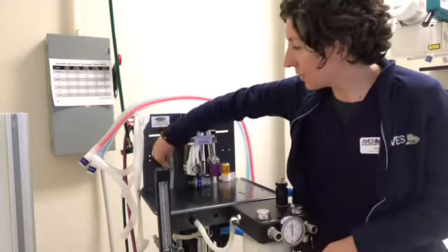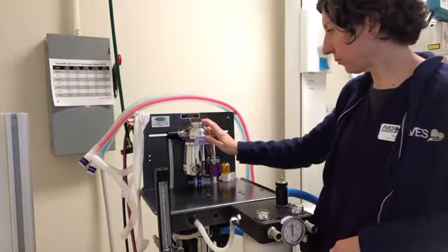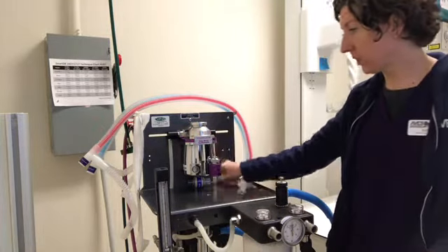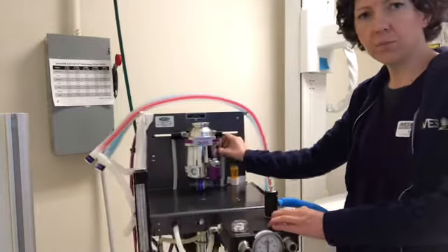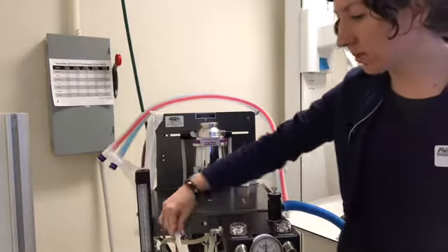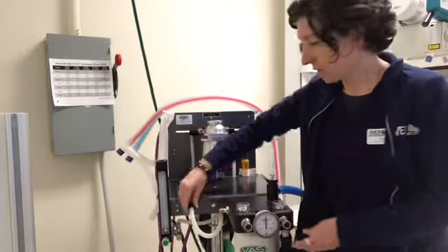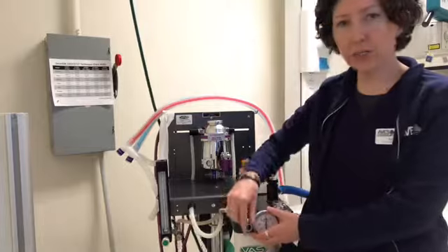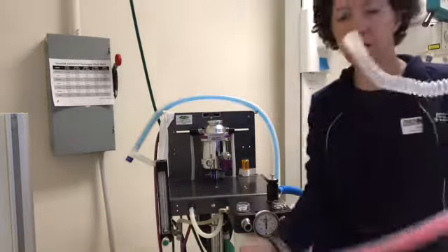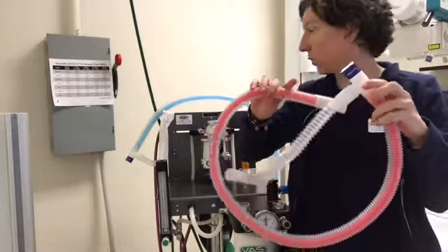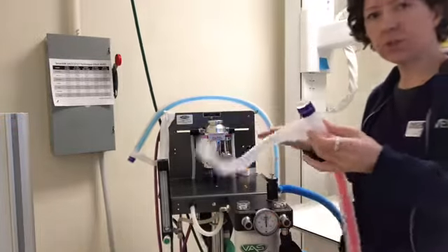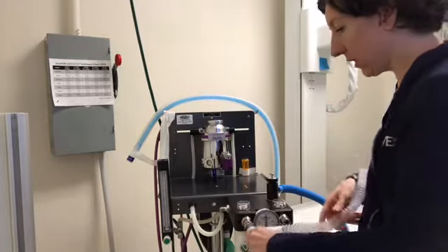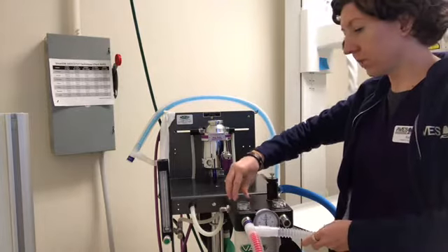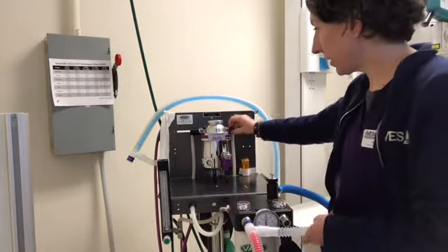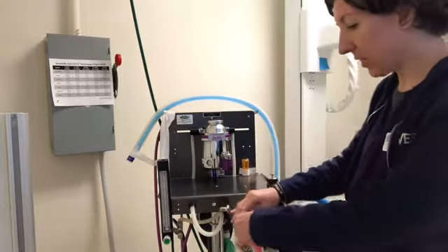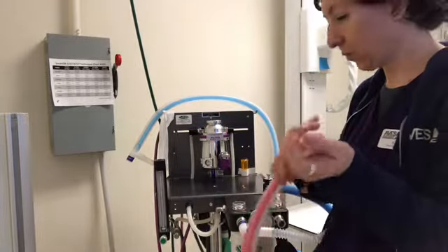Okay, and the vaporizer inlet port is this tubing right here, and it comes into the vaporizer. And then the outlet port is this tubing that comes right here, and this is where the anesthetic gas exits the vaporizer, comes around to the front here, and goes into the inhalation port, the unidirectional valve. So this is one of our rebreathing systems. How this works is the inspiratory valve goes into the inspiratory, inhalation unidirectional valve. It takes that anesthetic gas, the fresh gas, and this is where the patient breathes in that fresh gas.